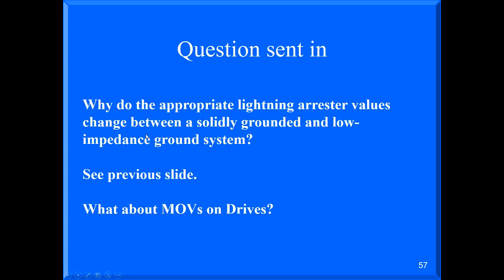In theory, I have zero current going through the neutral ground resistor, so it has no effect on me, my system, and what you've added. Your unbalanced loads, you shouldn't have any issues unless your protective relays are not set properly.